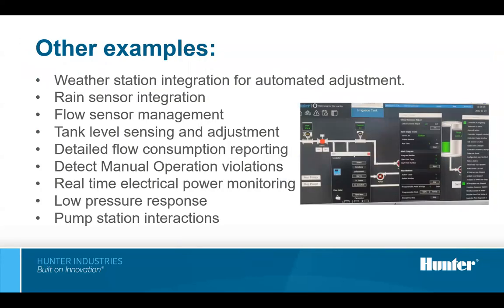Other examples of things that can be integrated. All we have to do is define what we want them to do. A weather station that's present in the SCADA, a rain sensor located elsewhere, flow sensors. There are flow sensors that can work with Modbus, TCP, or other protocols and report their flow data directly to the network. That information can then be used to adjust, cancel, or increase irrigation.